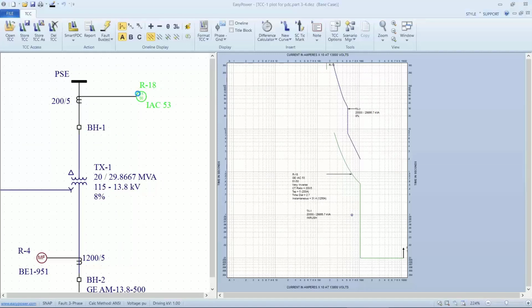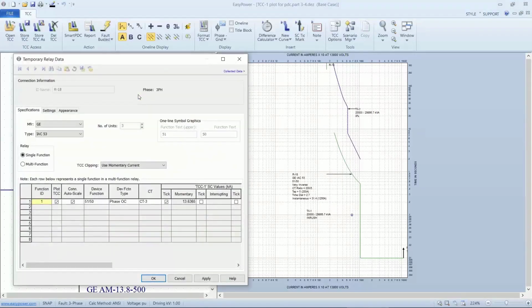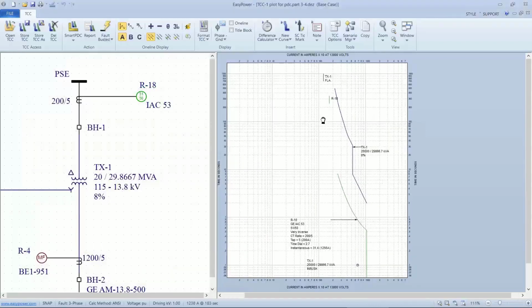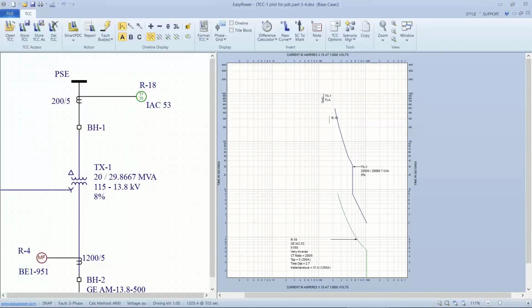Now again, we know the full load current was 150 amps, so let's see where that is. When we plot the TCC curve for the transformer, we get the full load current calculated for us in this tick mark up here. If I hover over it, I want to watch down here on the bottom information bar of the screen, and when I hover over that TCC plot, it tells me the max current is 1255 amps. Wait a minute, Jim, I thought you said the max current was 150 amps.